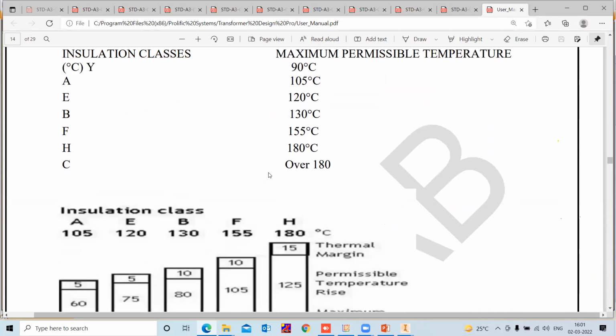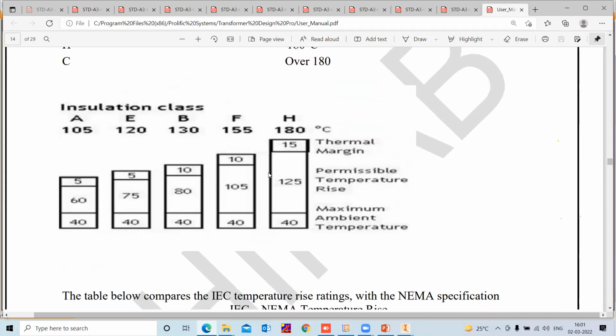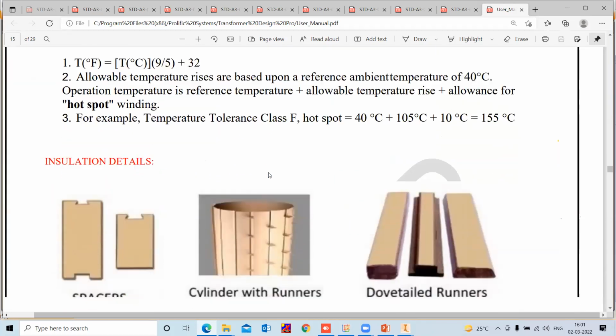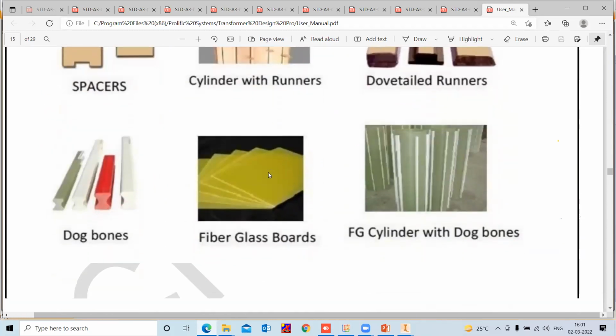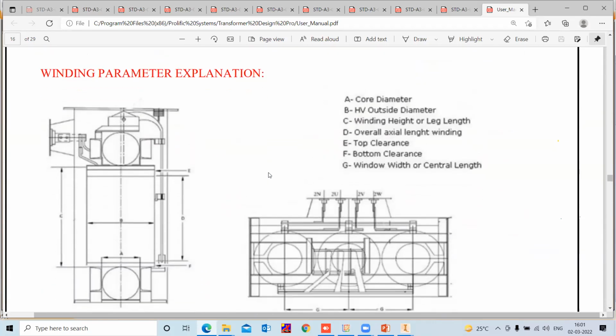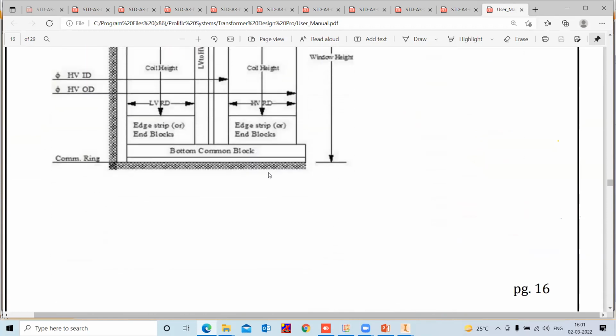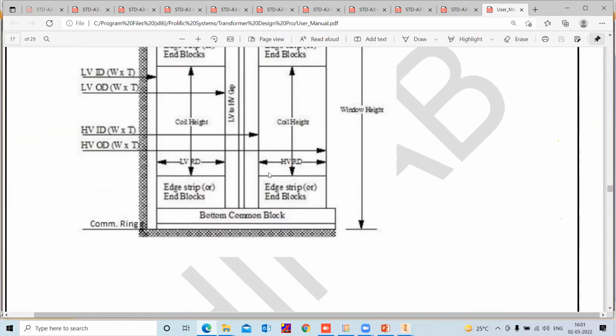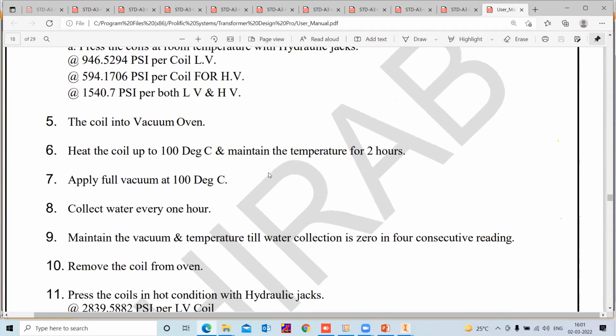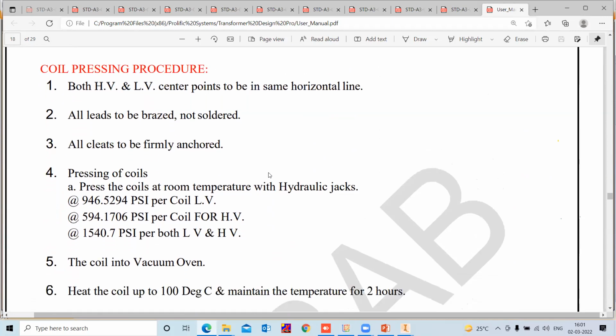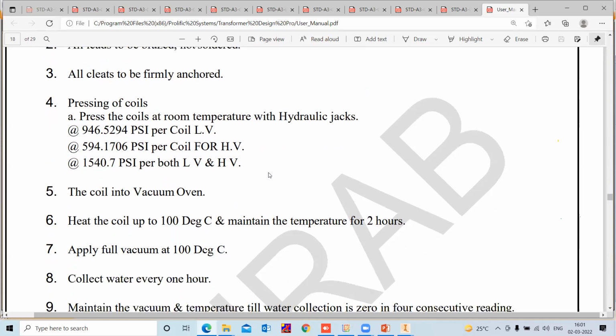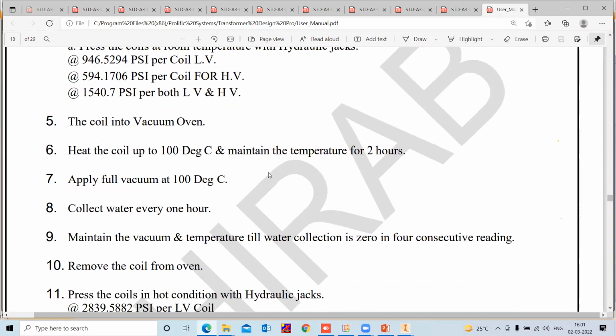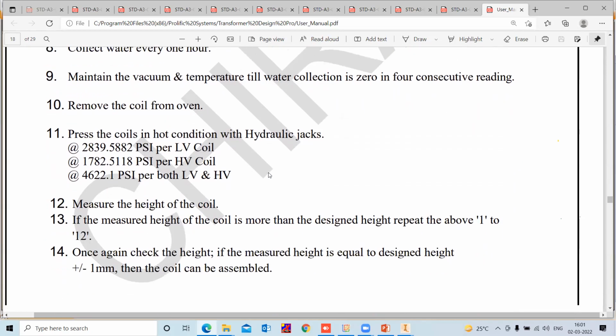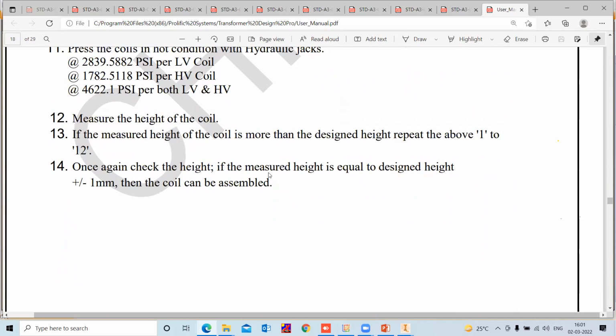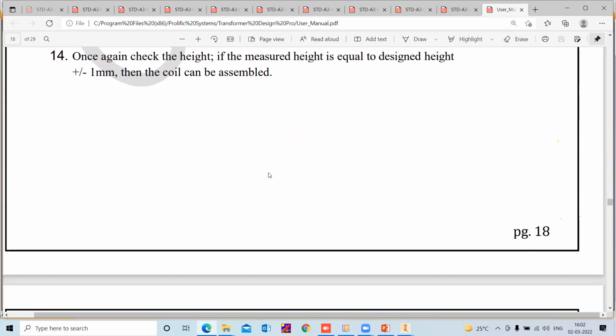Then the insulation classes. For dry type, it will take F and H type automatically. Then the insulation materials for dry type and all type transformers. Then some winding parameter explanations. Then the core coil assembly details for different kinds of core construction, like circular or elliptical construction. Thereafter, the coil pressing procedure, like how much pressure you have to give individual LV and HV coil and the combined, and how long the ovening time is and at what temperature. That information is given here. And after ovening, again how much pressure you have to give for individual and combined with the hydraulic jack. That information is given here.